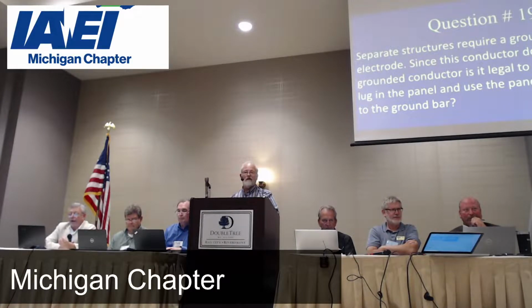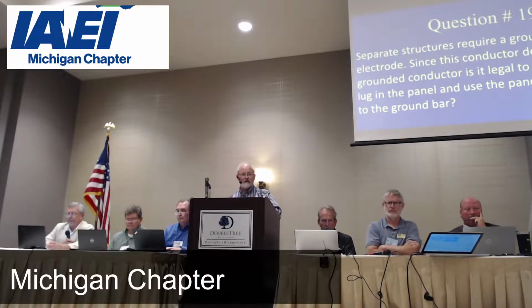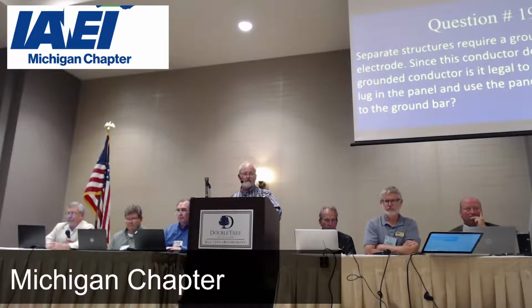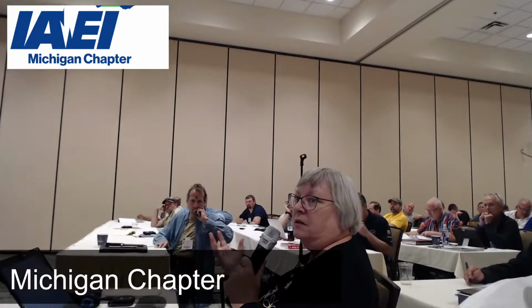But then you also clarified that the grounding electrode conductor has little to nothing to do with fault currents. So connecting it to the equipment grounding conductor is not as important as connecting a grounding electrode conductor to the fault return path at the service, which we also call the grounded conductor or neutral conductor. That's critical. That's where that grounding electrode conductor starts. It may or may not go to a grounding electrode, but my garage does need a contact with earth, and it could be the panel itself that is doing that when I lug onto the panel.